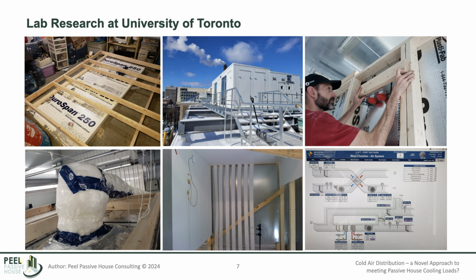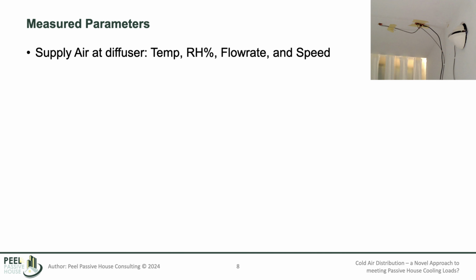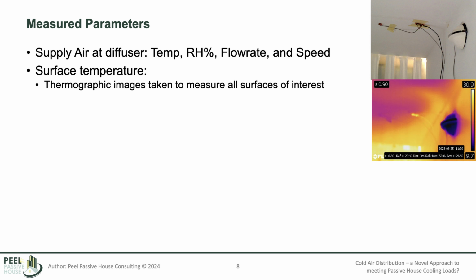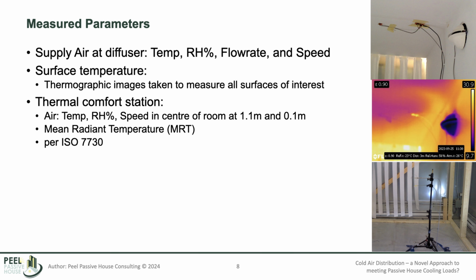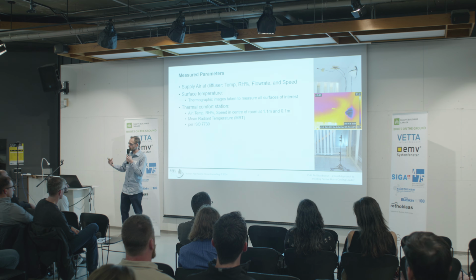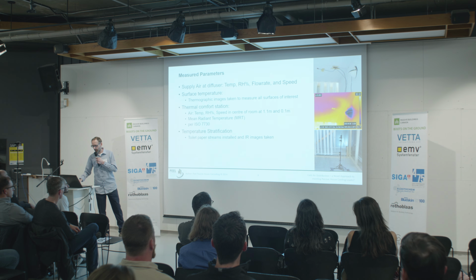Some of the things we measured: the conditions of the air coming out of the diffuser, like temperature, relative humidity, flow rate, and so on, plus surface temperature using an IR camera. We also had a thermal comfort station from the University of Toronto, a station that allows you to assess occupant comfort, which we placed in the center of the room to see how it performed.